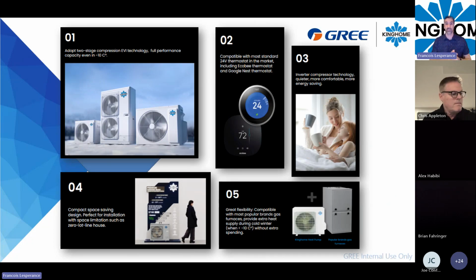This heat pump uses a two-stage inverter compressor, so it can modulate its power. This heat pump is 24 volt compatible, already built in. So you don't have communication issues between the indoor unit and the outdoor unit, because it will be simply a 24 volt connection from the thermostat to your furnace to the outdoor unit. It also has a small footprint compared to other types of unitary heat pump outdoor units, and that gives you great flexibility because it's compatible with any kind of indoor unit.